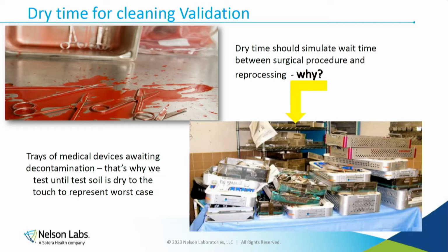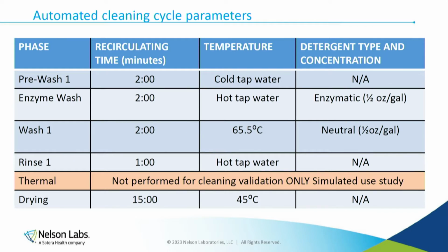But we challenge it with dry to the touch. So it has to be dry before we process. So we use worst case test soils, worst case contamination, and we dry them, okay? Three variables already worst case. And then we do the automated cleaning cycle, right? So for automated cleaning cycles, we have cycle parameters. I'm sure you've seen these cycles.